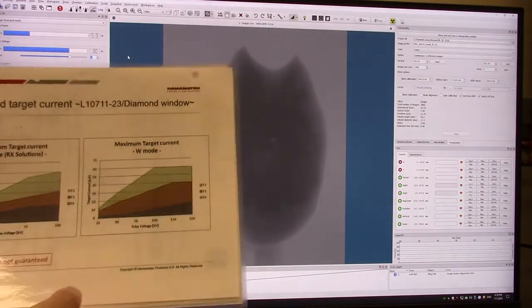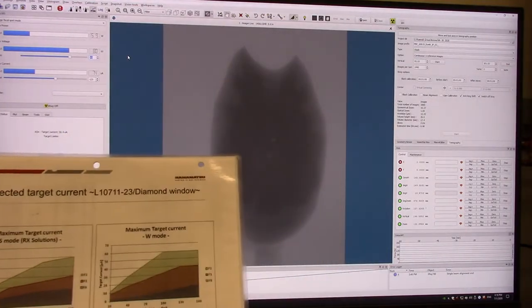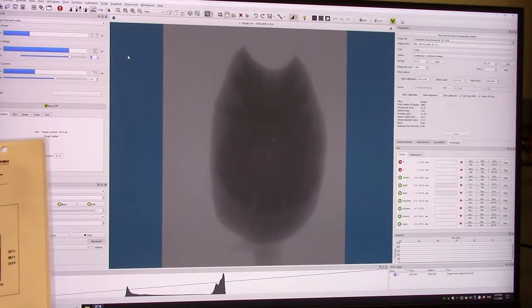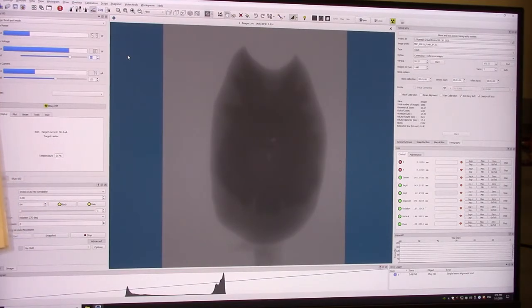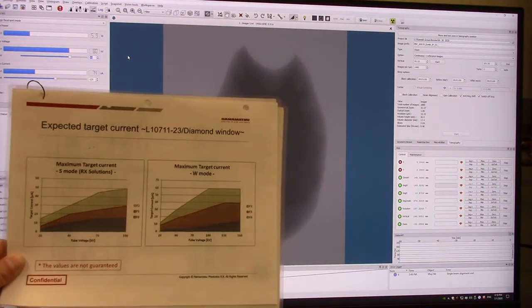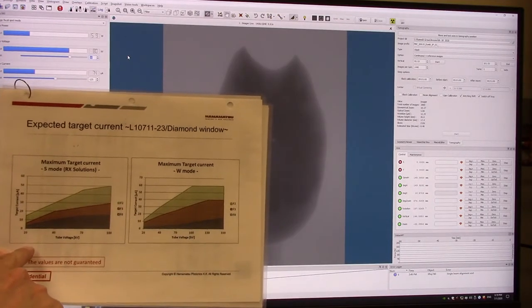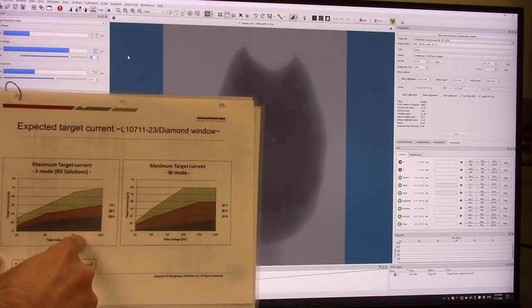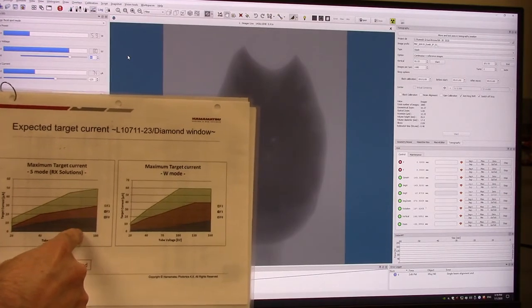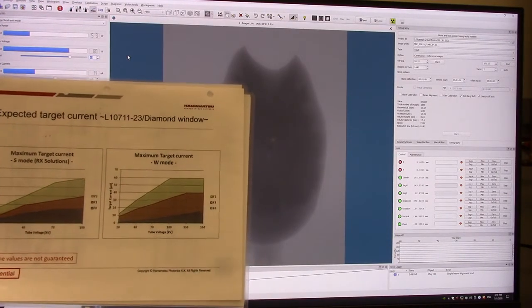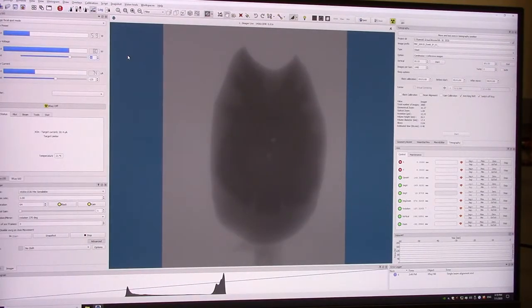another useful thing to check is the target current for your given focal spot mode and voltage. Currently it's 50.4 microamps, and if I look at this chart, I can see that for a tube voltage of 80, which would be about here, on the largest focal spot mode, I should have about 50 microamps. And I do, I've got 50.4.